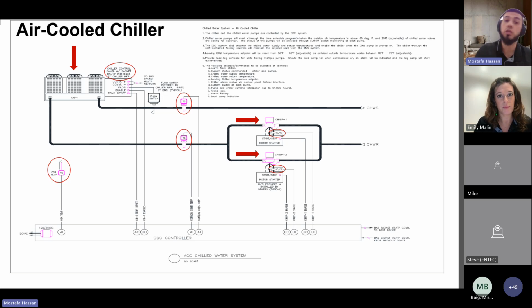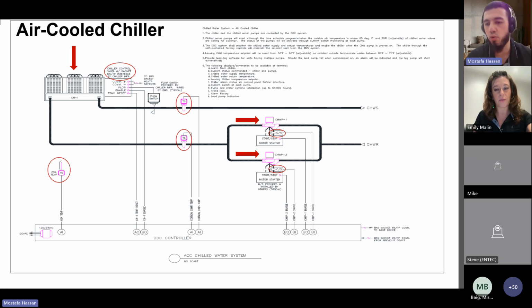So the most efficient way I've seen it is just doing it: if there's a VFD, utilize what's there, right? If there's an actual BACnet interface, connect it, pull the communication point to the BACnet interface, right? It's hardwired anyways, by the way. I don't know if you're making a distinction between one being hardwired and one not. But you mean like wiring up the current switch and not pulling data from the VFD? I think the way I've seen it is it's usually done at the VFD if it's available. So versus there being a motor there or just wiring up to the current switch.